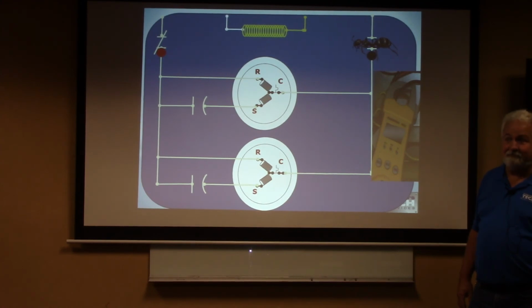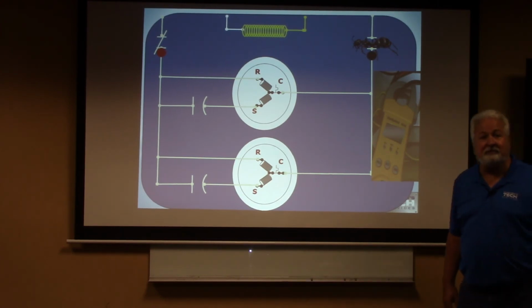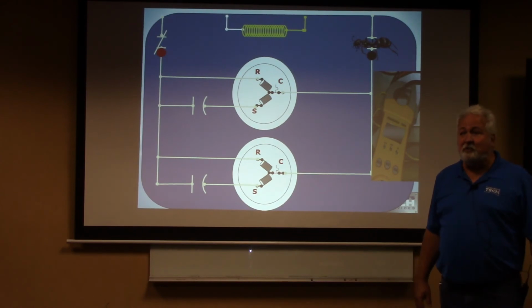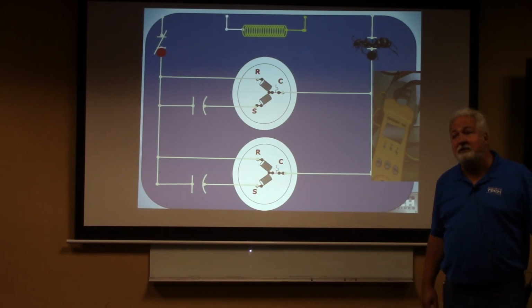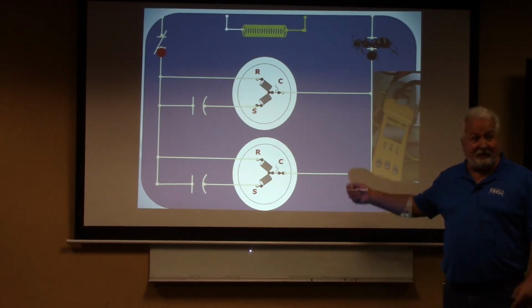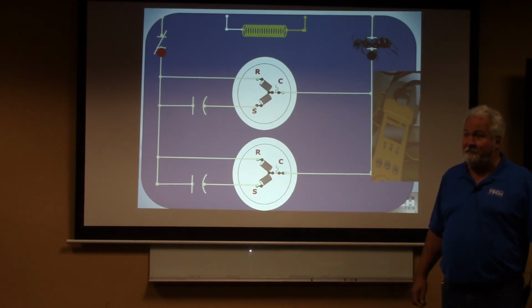Does that work? Good. And these are seasoned technicians. Okay? I'm not trying to beat anybody up here. I'm just saying this is what we find. So when we're trying to use our meter, we need to know what our meter is going to tell us before we stick our meter on there. Is that right? Because if I got 120, that means something has got a ground on it. Does that make sense? Because I got an L1 potential and I got a ground potential somewhere. Or a neutral potential, yes?